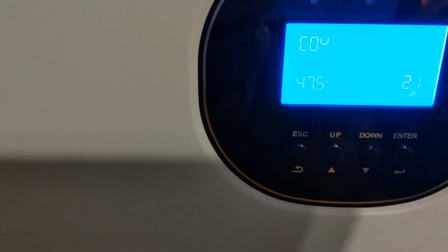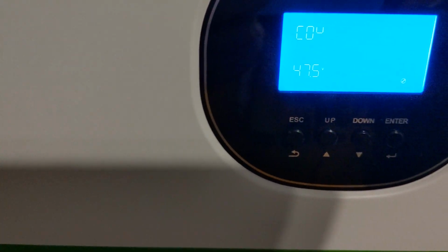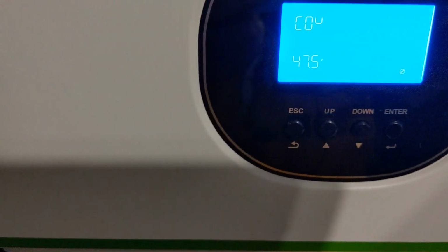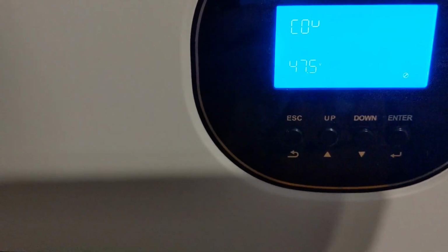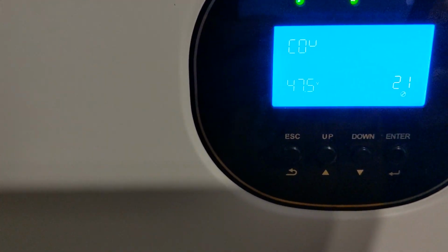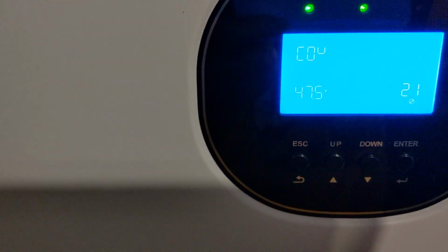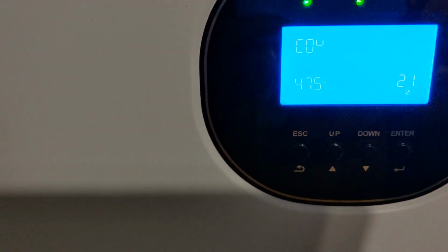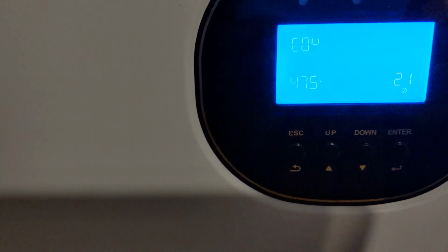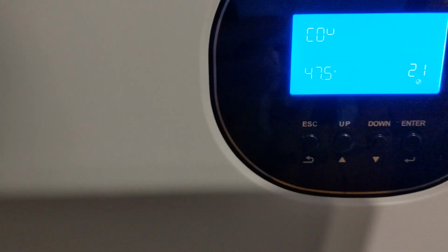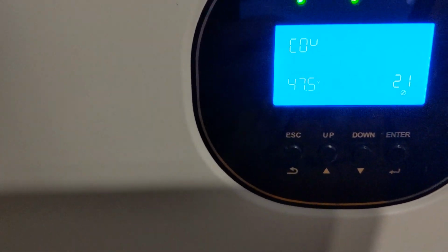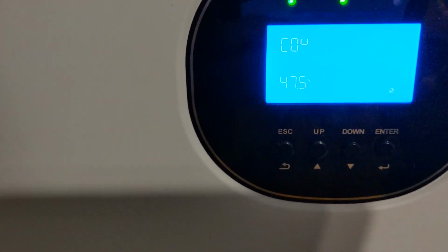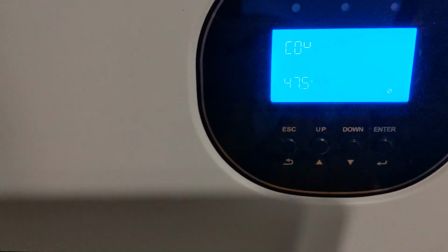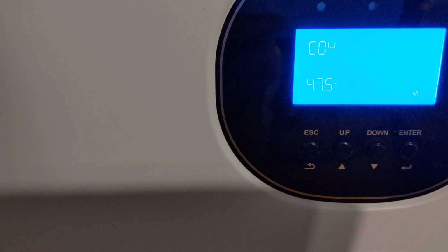This is your low voltage DC cutoff. This is where you set the voltage you never want to exceed for your low battery voltage. So if you know that your batteries are down to say 10% capacity remaining when it hits whatever set voltage it is, and in the case of mine, about 47.5, that leaves about 5 or 8% left in the battery. That's what you would set in here.